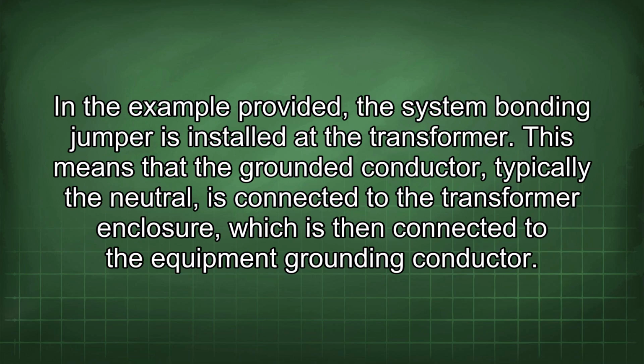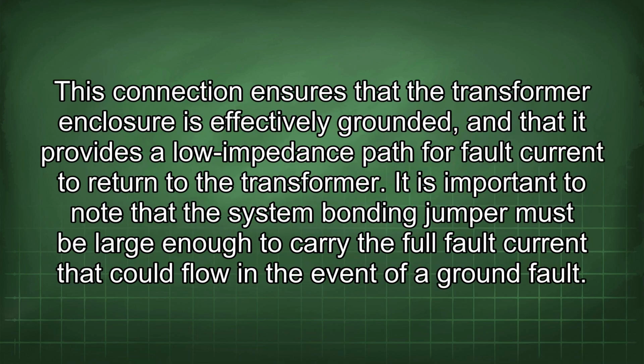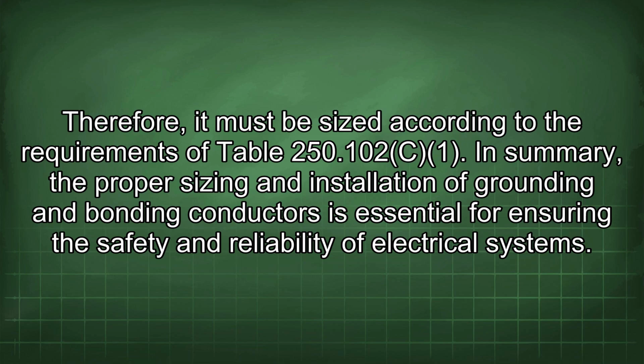In the example provided, the system bonding jumper is installed at the transformer. This means that the grounded conductor, typically the neutral, is connected to the transformer enclosure, which is then connected to the equipment grounding conductor. This connection ensures that the transformer enclosure is effectively grounded and that it provides a low impedance path for fault current to return to the transformer. It is important to note that the system bonding jumper must be large enough to carry the full fault current that could flow in the event of a ground fault.